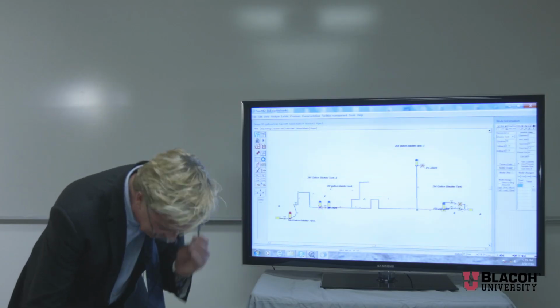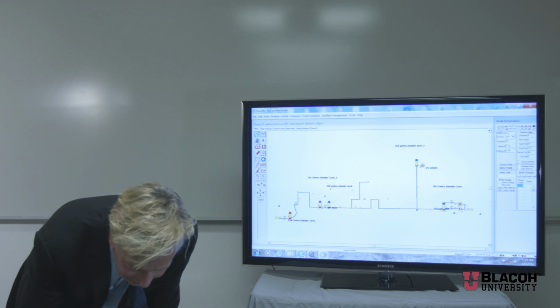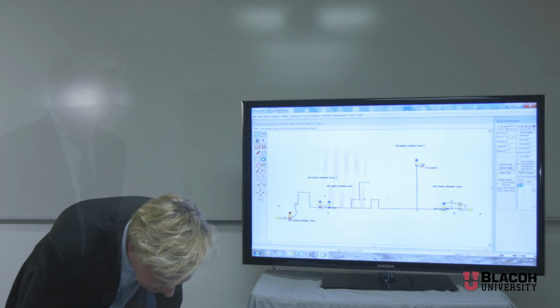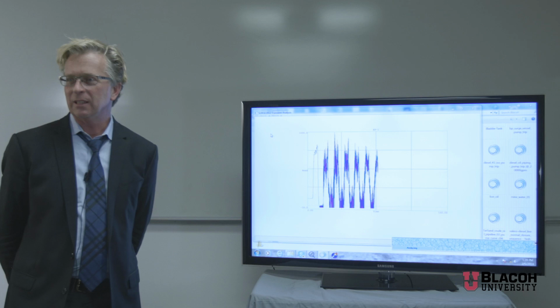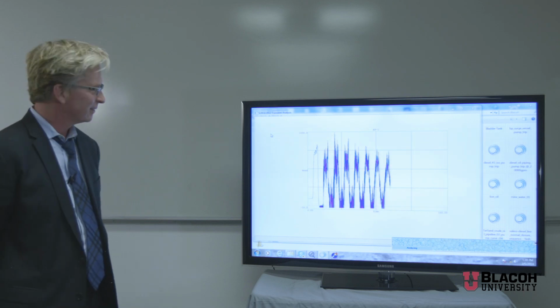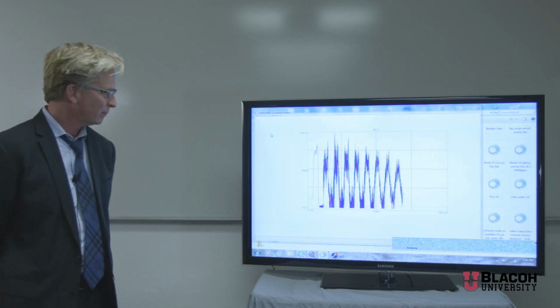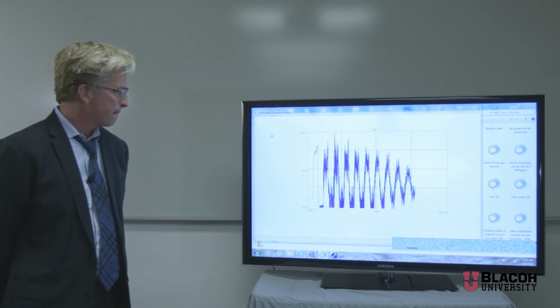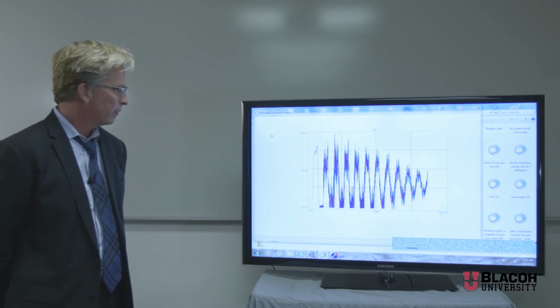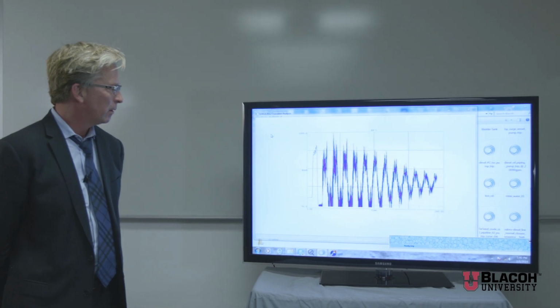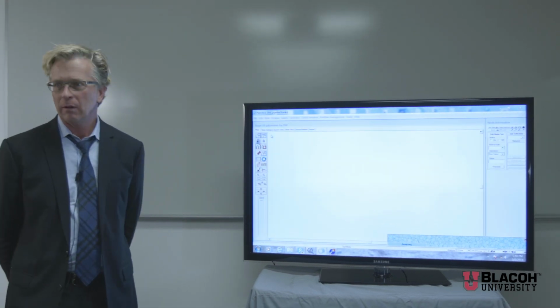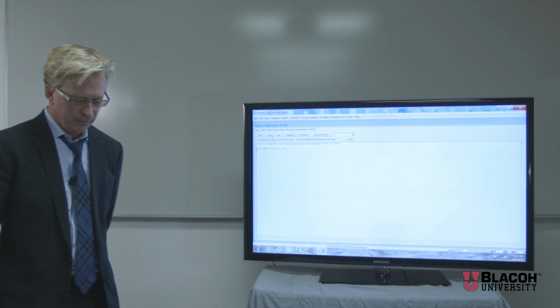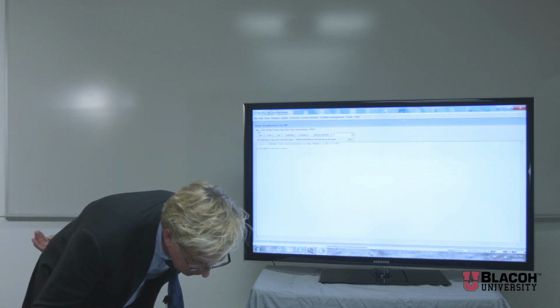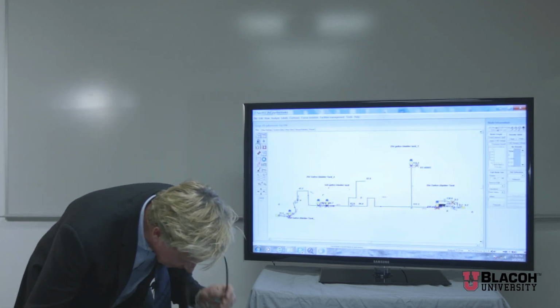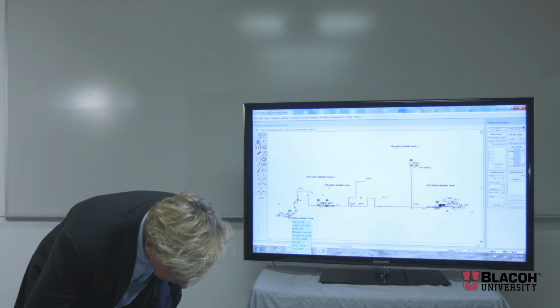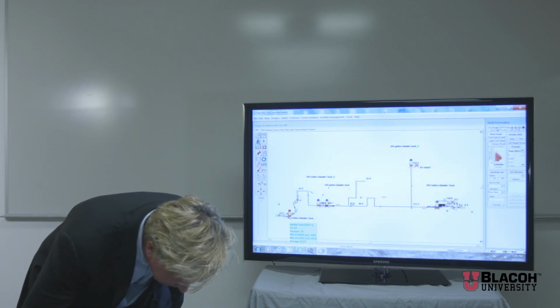So let's just look at it. We'll take the surge vessel out of service and look at the cause and effect of what's happening in the system. So a lot of stress on the piping system. So you actually needed to have more than one surge suppressor in that system. One next to the valve. Yeah, so in reality, the Coast Guard would not let me put in this vessel.